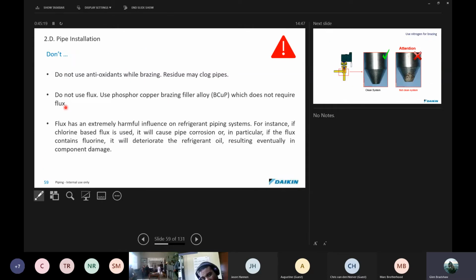Do not use antioxidants and do not use flux. Use phosphor copper brazing filler alloy, that's your normal copper rods. Flux has an extremely harmful influence on refrigerant piping systems. For instance, if it's chlorine based and it's used, it will cause pipe corrosion. In particular, if the flux contains fluorine, It will deteriorate the refrigerant oil, resulting in eventual component damage. So do not use rods that are flux coated, or any flux material that you might have, like some of these that you have to paint onto the piping. Only use phosphor copper brazing filler rods when welding.